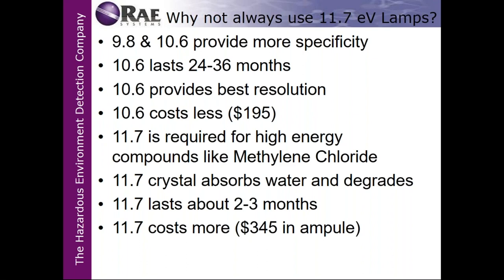I have turned down orders for 11.7 lamps because people were going to be waiting too long to install the 11.7 lamp, which means that they wouldn't insert it into their monitor for at least 30 days. They'd basically be wasting their money. So they usually order an 11.7 lamp when it's time to use it, and they charge the customer. It's customary to charge the customer as part of your fee when you go out and do an investigation with an 11.7 lamp. It's a casualty of war as far as I'm concerned.